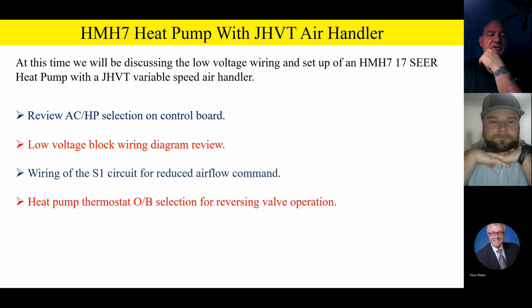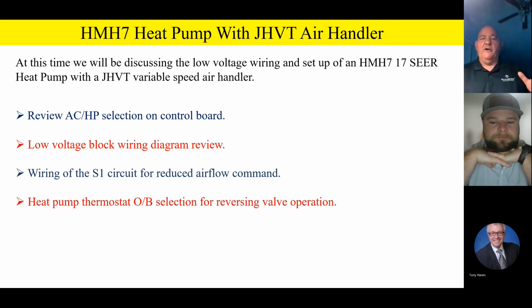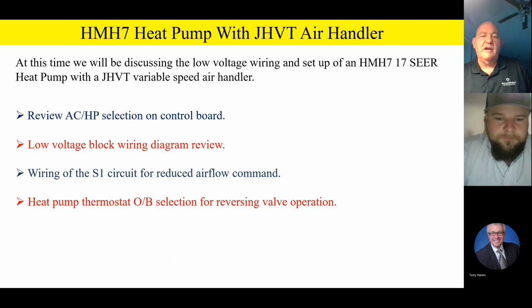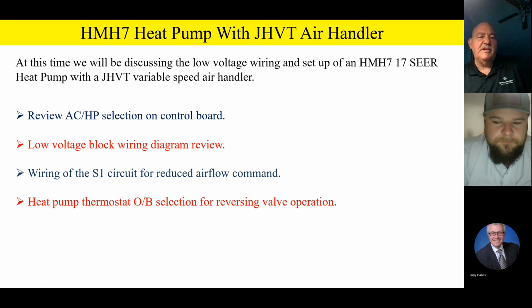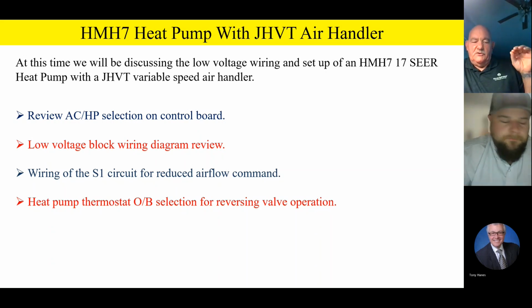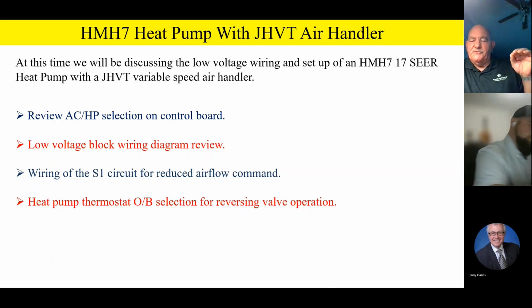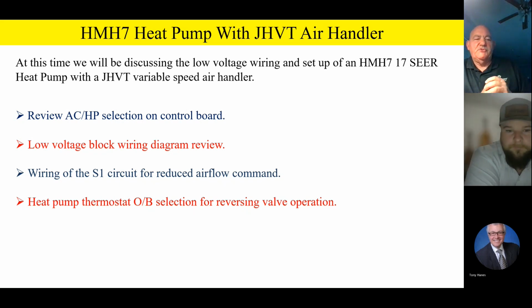All right, so team, this morning at this time, we're going to be actually talking about some low voltage wiring and the setup of the JHVT air handler along with the HMH7 heat pump. So the first thing we're going to do, we're going to talk about how to set up and review the control board. There's actually a dip switch there, or a selection that's going to give you either AC or heat pump. It's really, really important that we select HP off the control board, and we'll show you where those switches are here in just a second or two. We're also going to discuss a low voltage block wiring diagram, as well as the S1 circuit for reduced airflow command.